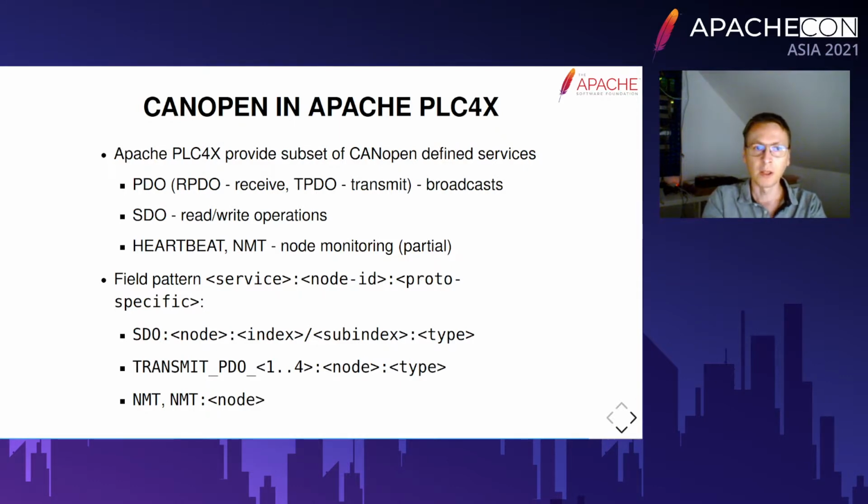So we do have support for process data objects, so PDO can be either receive or transmit, those are broadcast messages. We also have SDOs, which are read-write operations. So as you can see, while we do not have read-write operations for generic CAN, we do have read-write operations on top of the CAN bus using CANopen. And besides that, we also have support for heartbeat and node monitoring.